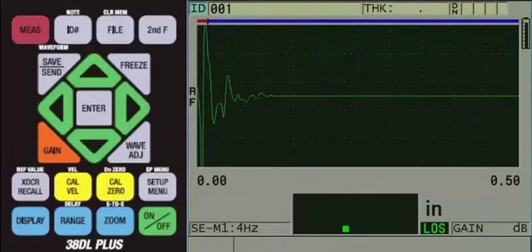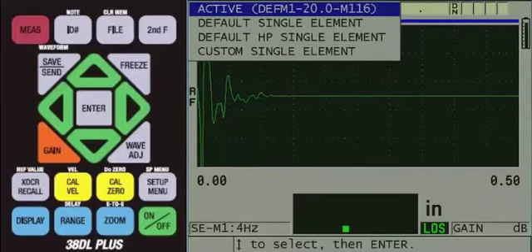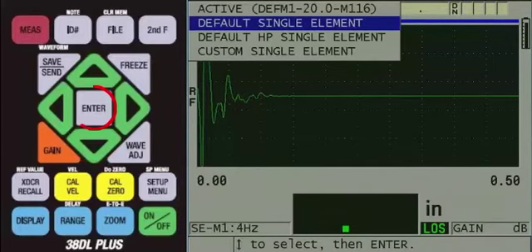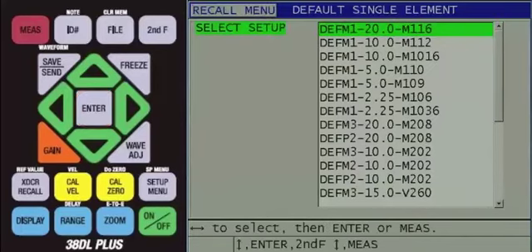Once the instrument is on, press the XDCR recall key. If we were using a transducer with a frequency lower than 2.25 MHz, we would need the HP software option and would choose default HP single element. However, since we are using a 2.25 MHz transducer, we will press the down arrow to default single element and then press Enter. Here you will see the list of default single element transducer setups.